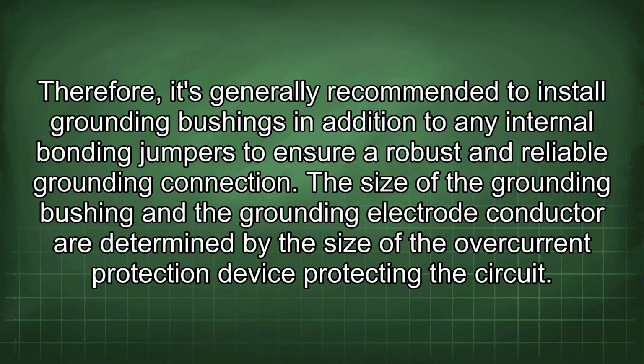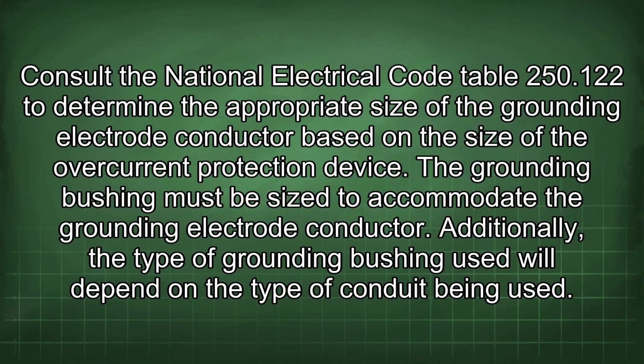reliable grounding connection. The size of the grounding bushing and the grounding electrode conductor are determined by the size of the overcurrent protection device protecting the circuit. Consult the National Electrical Code Table 250.122 to determine the appropriate size of the grounding electrode conductor based on the size of the overcurrent protection device. The grounding bushing must be sized to accommodate the grounding electrode conductor. Additionally, the type of grounding bushing used will depend on the type of conduit being used.